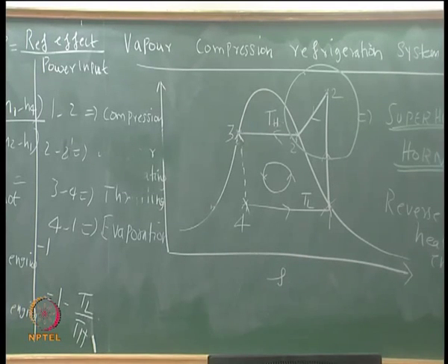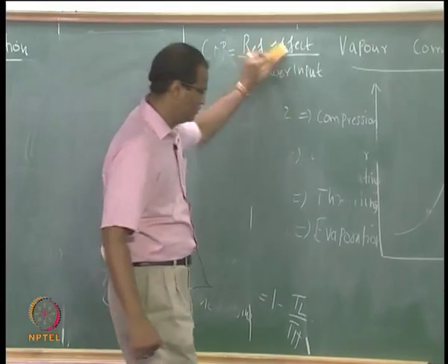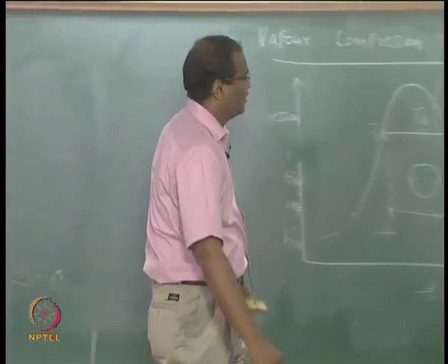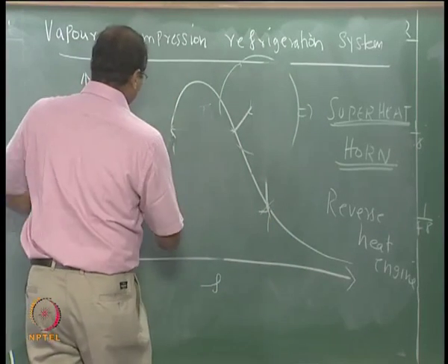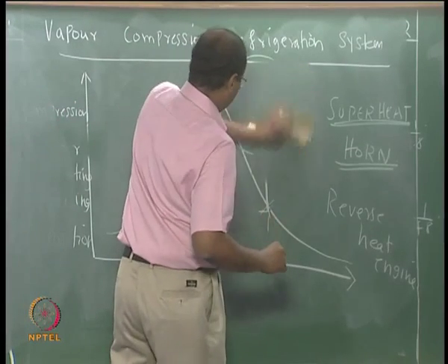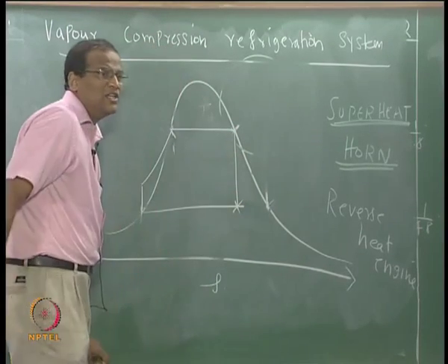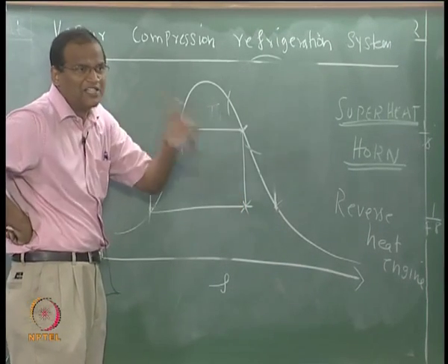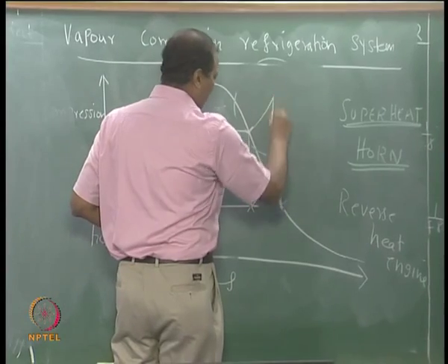If you reverse the direction of the arrows, you get a Rankine cycle power plant, correct? So the Rankine cycle power plant will be like this. So if you do this, it will be an extremely wet mixture at the end of the expansion. If it's less than 88%, it will cause erosion of the blades. Therefore, we superheat it and bring it.